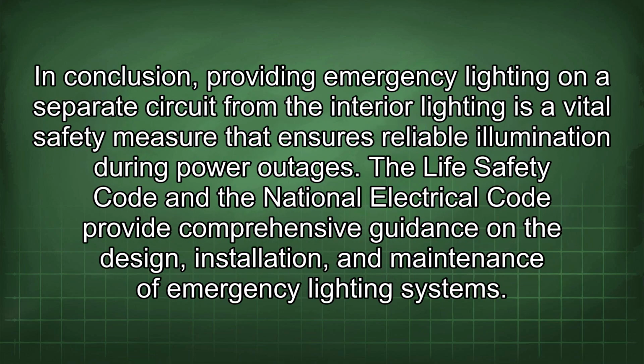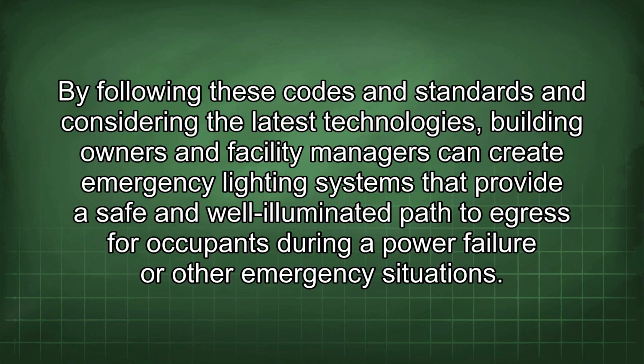In conclusion, providing emergency lighting on a separate circuit from the interior lighting is a vital safety measure that ensures reliable illumination during power outages. The Life Safety Code and the National Electrical Code provide comprehensive guidance on the design, installation, and maintenance of emergency lighting systems. By following these codes and standards and considering the latest technologies, building owners and facility managers can create emergency lighting systems that provide a safe and well-illuminated path to egress for occupants during a power failure or other emergency situations.